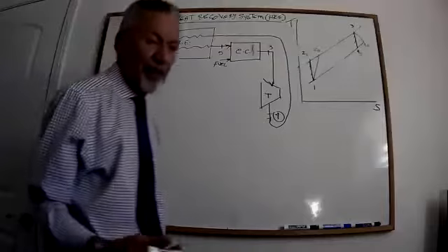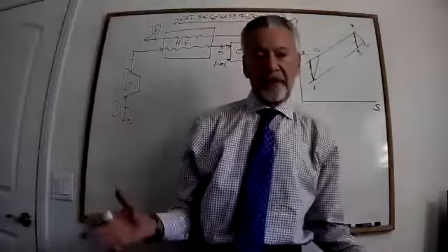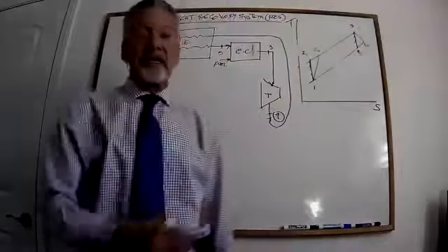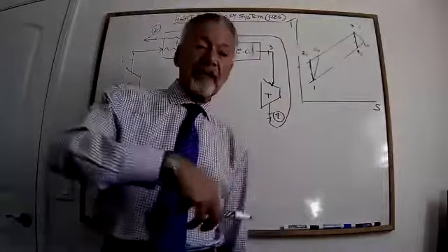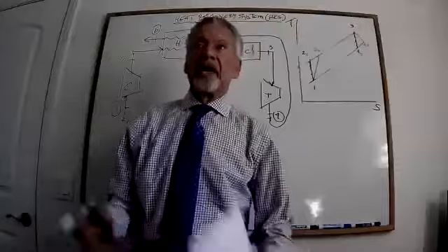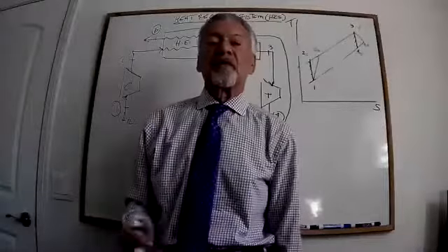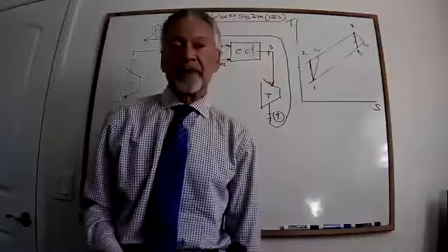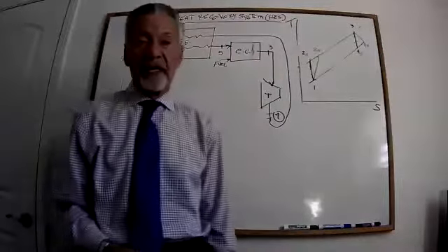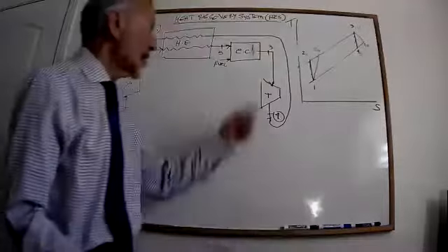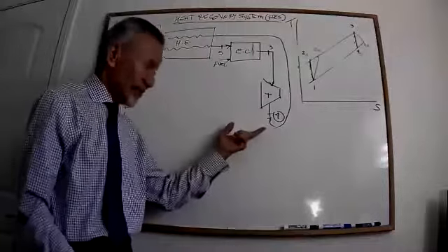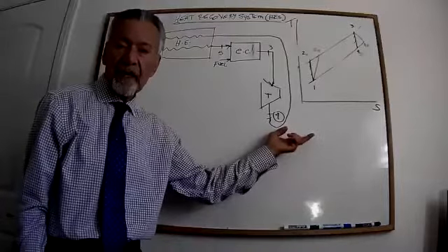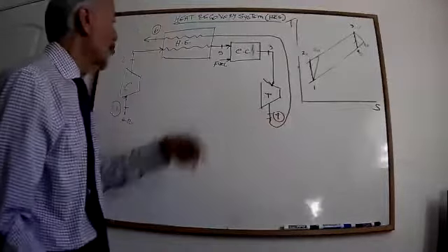If you go to LA Harbor College, I designed an air conditioning system there that has a gas turbine. We recover the heat and we have an absorption chiller. We provide chilled water to cool off the campus through that heat recovery system. So we can do a lot of things instead of just exhausting everything to the atmosphere. So that is how we modify.